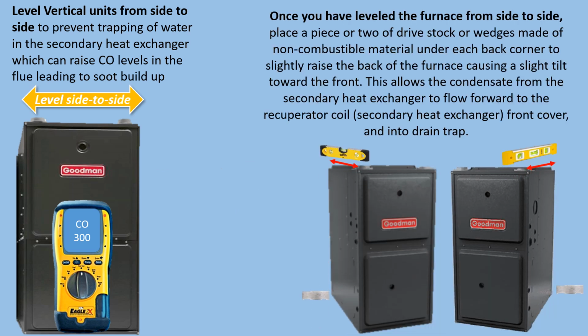Once you have leveled the furnace from side to side, place a piece or two of drive stock or wedges made of non-combustible material under each back corner to slightly raise the back of the furnace, causing a slight tilt towards the front. This allows the condensate from the secondary heat exchanger to flow forward to the recuperator cover, secondary heat exchanger front cover, and into the drain trap.